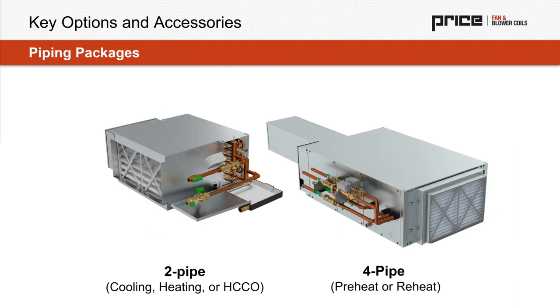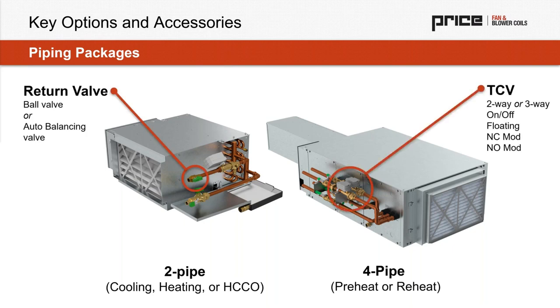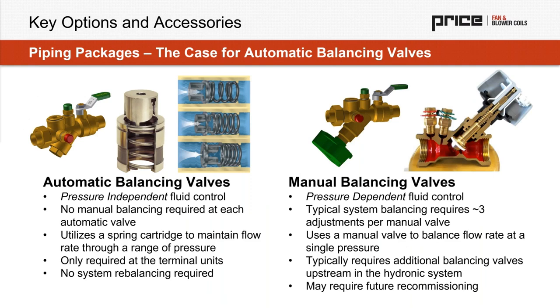The last thing I want to close out with is piping packages. So piping packages are more common on fan coils to come from the factory than what we would see on a lot of other products, like a classic reheat valve. And the big reality here is whatever you specify as an engineer, whatever your piping schematic is, really that option is available on a fan coil as well. My only pitch, and the one thing I want to note, is maybe a bit of a recommendation on why specifying auto balancing valves makes some sense instead of manual balancing valves.